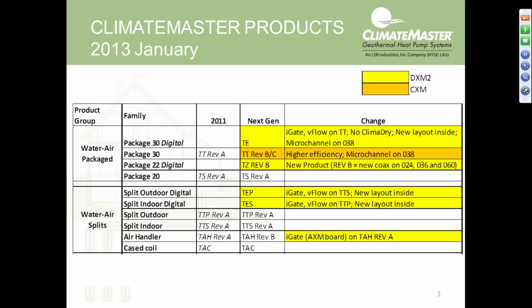Now in our air handlers, the TAH Rev A is the non-communicating air handler, still available. And then the TAH Rev B is the new communicating air handler, in order to work properly with the TEP and the TES. We'll go into more details on how things can be interchanged in a few other slides coming up. The Rev B has a new control board called the AXM board that will communicate with the DXM2 board in the TEP and the TES. It also can be connected to a non-communicating split if that were to happen out in the field.